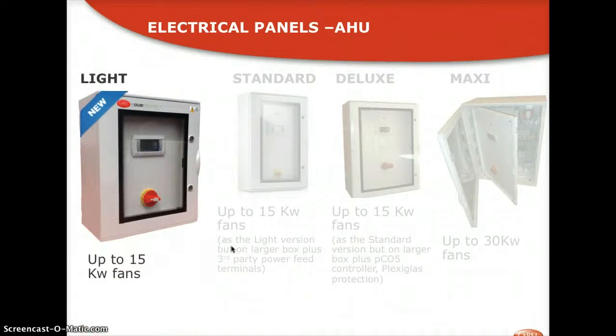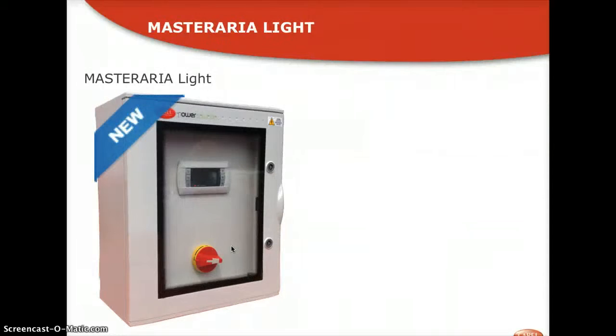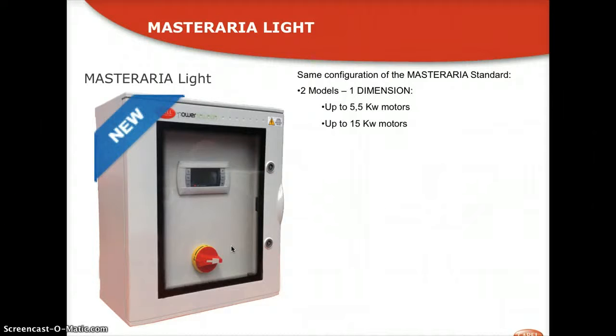Now, we have introduced a new range, a new cost-effective line of products in the air handling unit panels, which is the Masteraria Light, which will cover fans up to 15 kilowatts, like all the other electrical panels. However, it still comes in two models with one dimension, 5.5 kilowatts and 15, to manage still two fans, supply and extract, and an extra contactor for all those auxiliaries, these devices which we've spoken about earlier on.